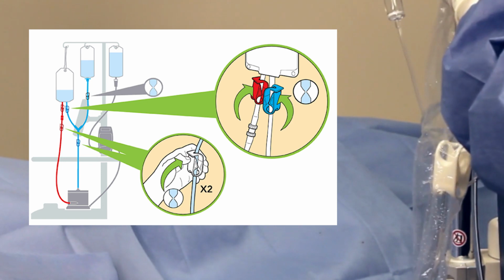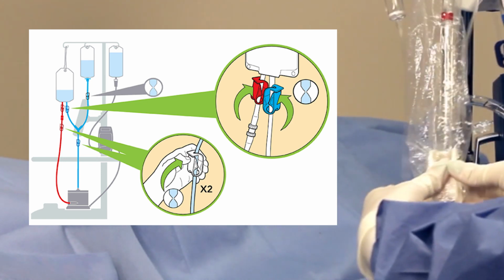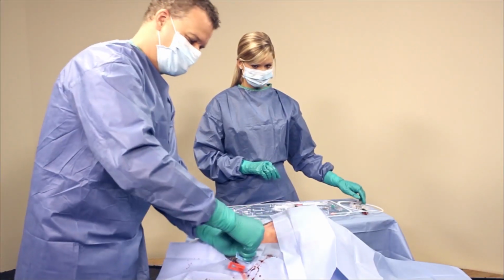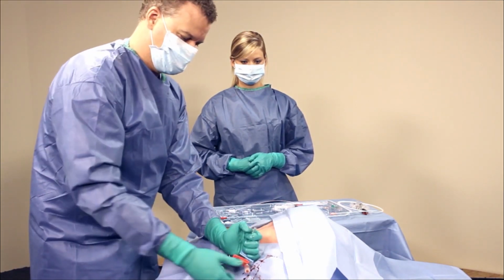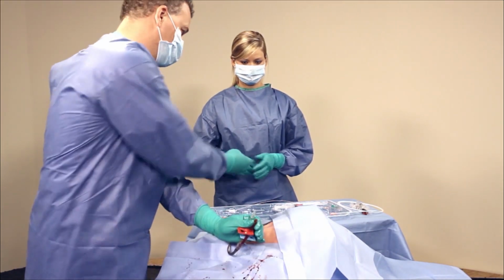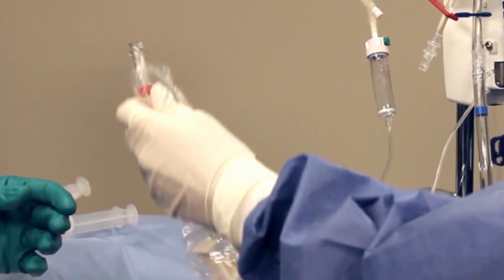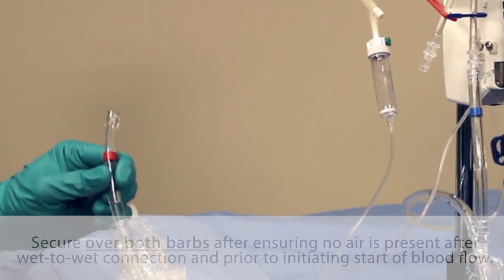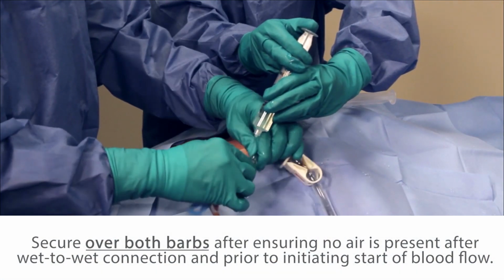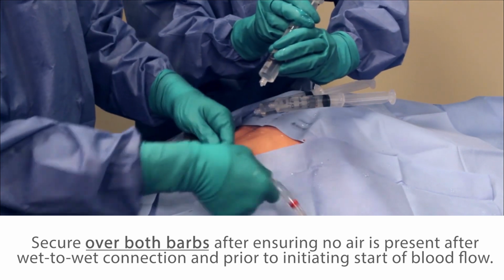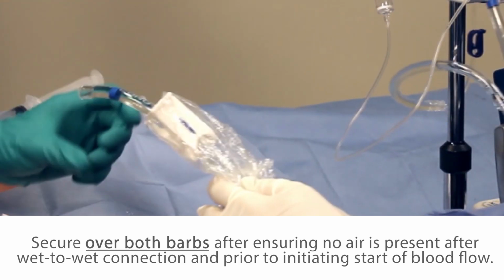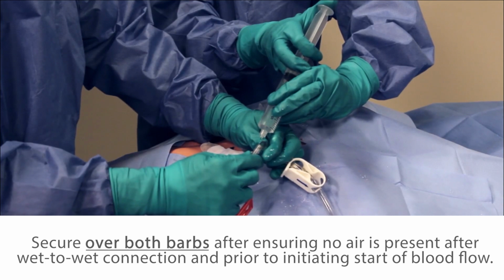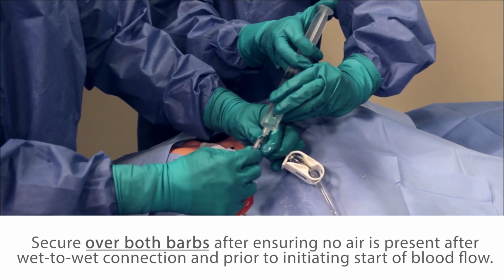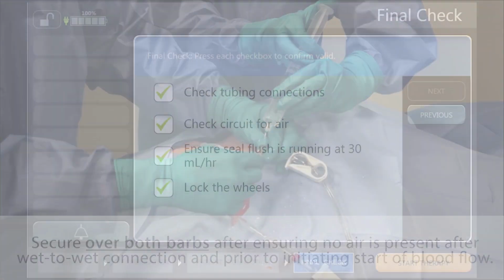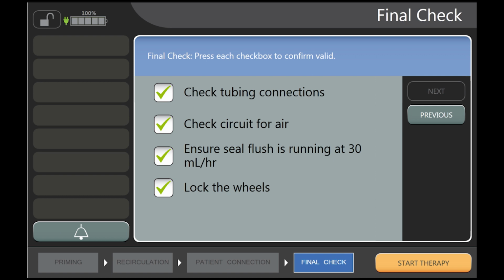Close all clamps in the circuit. Remove the priming adapters from each catheter lumen prior to connecting blood tubing. Disconnect the red tubing from the recirculation bag and connect it to the red lumen on the catheter using a wet-to-wet technique. Disconnect the blue tubing from the Y connector and connect it to the blue lumen on the catheter using a wet-to-wet technique. Open all clamps.